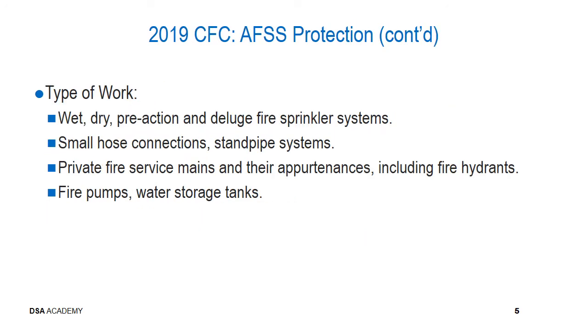Types of work that will be encountered with our fire protection system. The sprinklers may be of the wet, dry, pre-action, or deluge types of design. May include small hose connections and standpipe systems. Private fire service mains and their appurtenances, which include fire hydrants. And potentially fire pumps or water storage tanks in those areas where there is insufficient pressure or insufficient water.